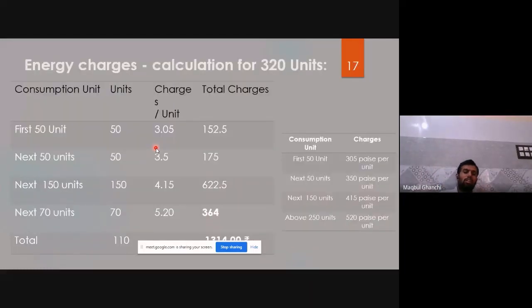Now let me give another example: if a person consumes 320 units, how do I calculate this? First, 50 units based on 3.05 rupees, so first 50 units at 3.05 gives an amount of 152.5. So the number of units has to be segregated based on this table. From 320, first 50 units charged at 3.05 rupees. Next 50, that is 51 to 100, charged at 3.5 rupees, giving 175 rupees. Next 150, that is 101 to 250, so total 150 units charged at 4.15 rupees as per PGVCL tariff structure, giving total amount of 622.5.